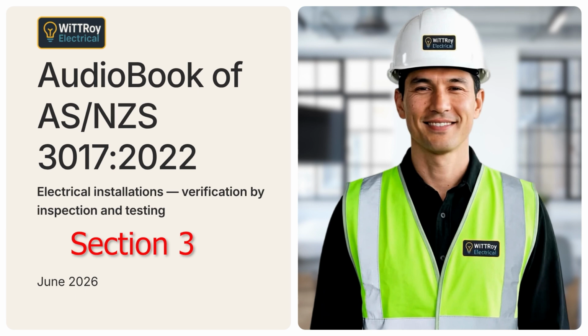Particular installation conditions must be checked. This may include underground wiring, aerial wiring, and safety services. Segregation from other services and other electrical installations must be checked. Protection against external influences must be checked, including the use of suitable enclosures where required. In simple terms, wiring systems must be the right type, the right size, correctly identified, properly supported, correctly protected, and suitable for the environment.